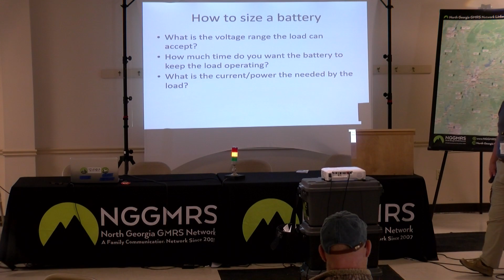The range is 10.5 volts to 14.4. 14.4 is pretty high, but that's when you're equalizing a battery. You'll get up to that high voltage, but the definition of a discharged lead acid battery is 1.75 volts per cell times, in this case, 6 cells, which comes out to be 10.5 volts. So when that battery hits 10.5 volts, it's considered to be fully discharged.